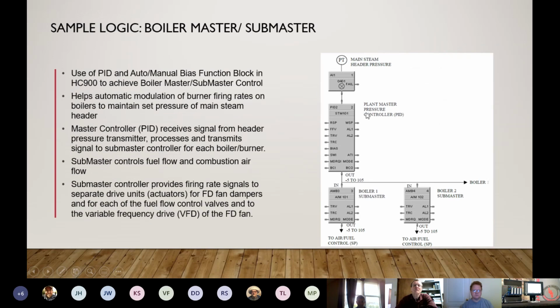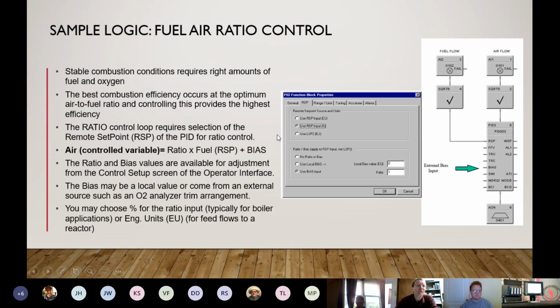Boiler master, submaster, again, here's a function block scheme tied together. You have your analog input for your main steam header. You have your plant master pressure control loop. So this is your UDC controller. And then you have your output going to boiler 1 submaster, boiler 2 submaster, and tied to fuel air ratio. Fuel air ratio control, again, we have our fuel flow, our air flow, square root. If you don't have a smart transmitter, the way that you extract flow is by using a square root extractor. So we have a square root math block tied to the analog input, going to a PID block, and then tied to our fuel air ratio output.